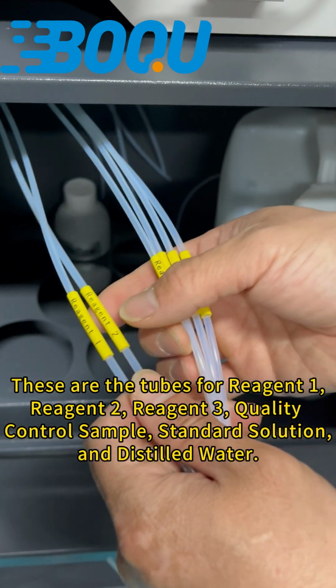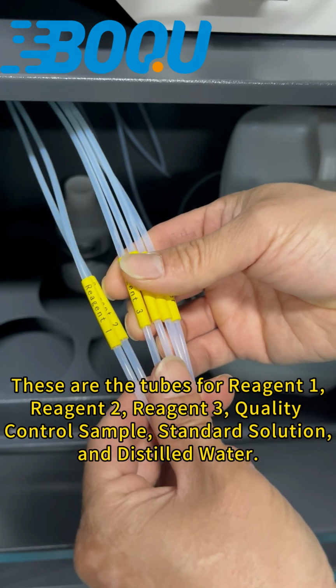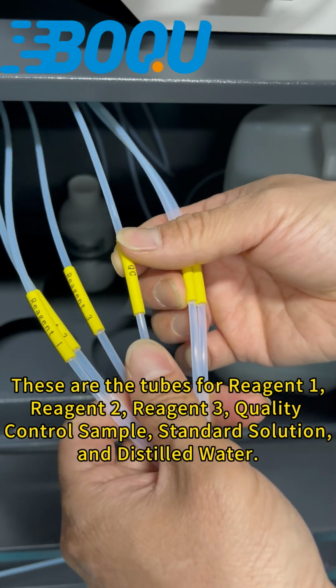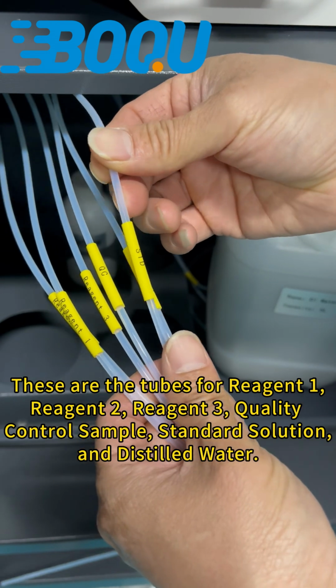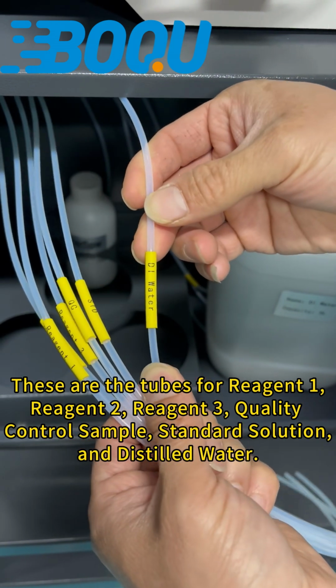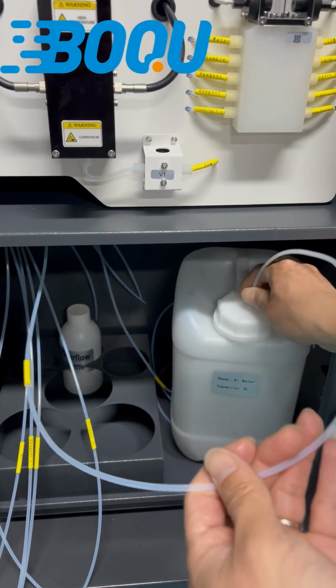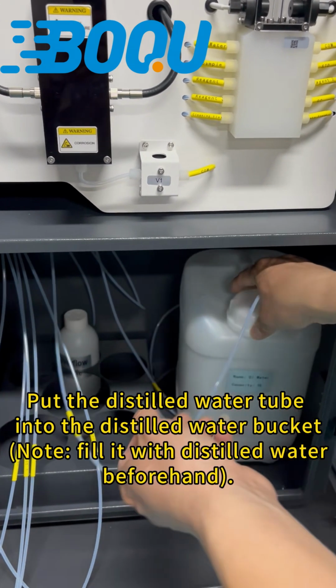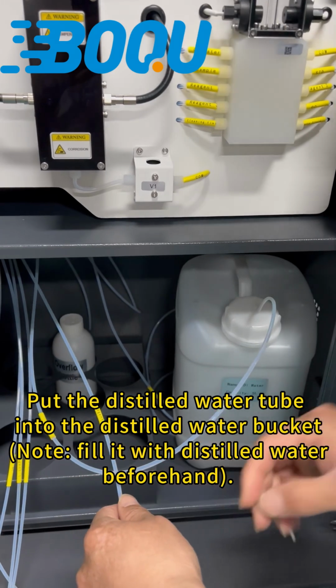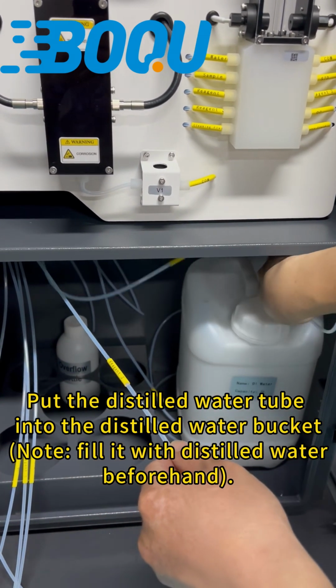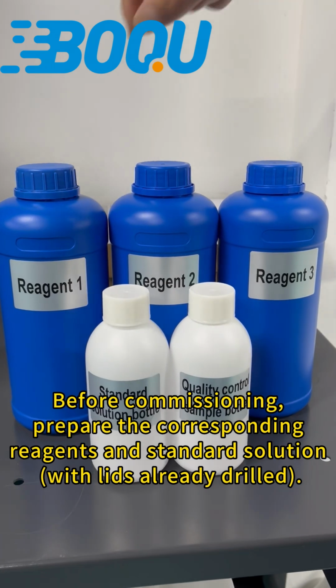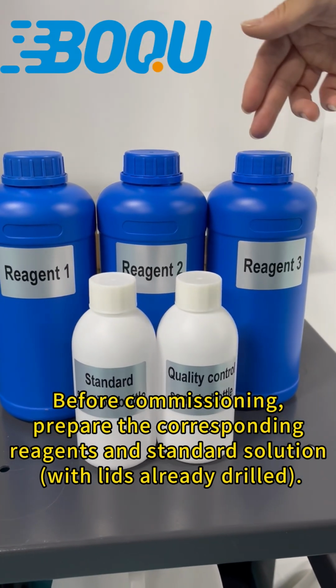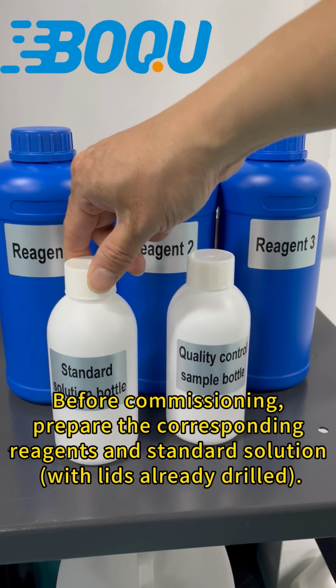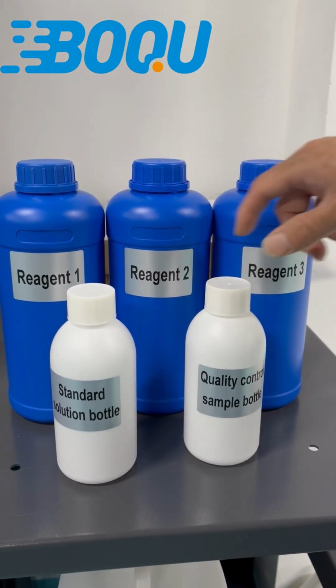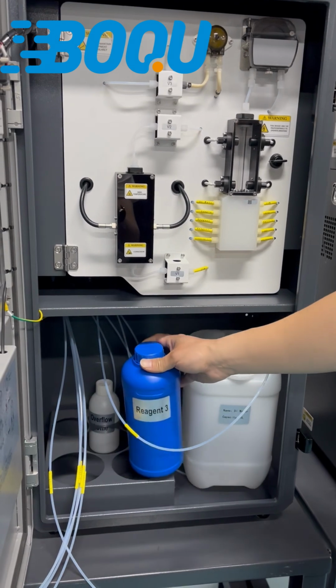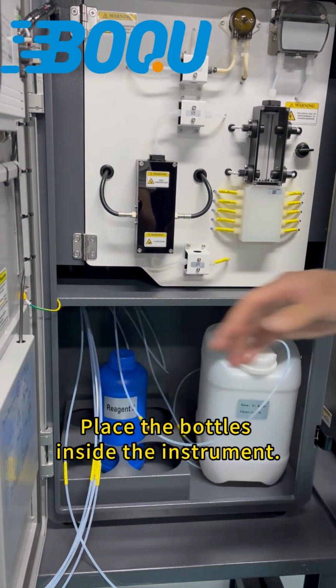These are the tubes for reagent 1, reagent 2, reagent 3, quality control sample, standard solution, and distilled water. Put the distilled water tube into the distilled water bucket. Note, fill it with distilled water beforehand. Before commissioning, prepare the corresponding reagents and standard solution with lids already drilled. Place the bottles inside the instrument.